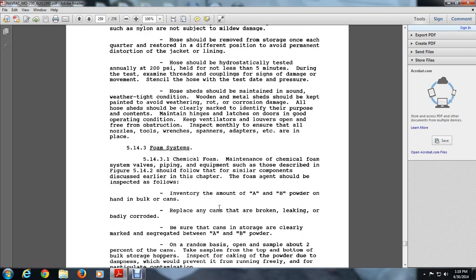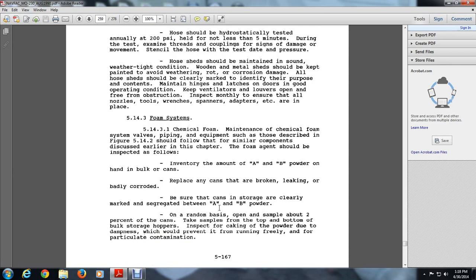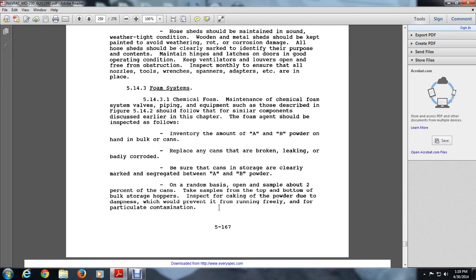Be sure the storage cans are clearly marked and segregated between A and B powders on a random basis. Open and sample about 2% of the cans. Take samples from the top and the bottom of the bulk storage hoppers to inspect for caking of the powder due to dampness, which would prevent it from running freely, and for particulate contamination.